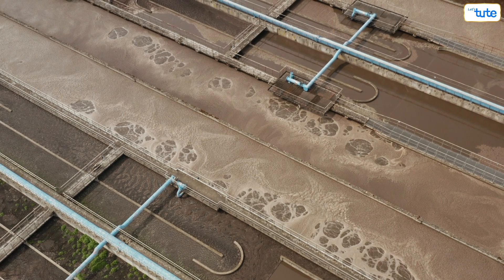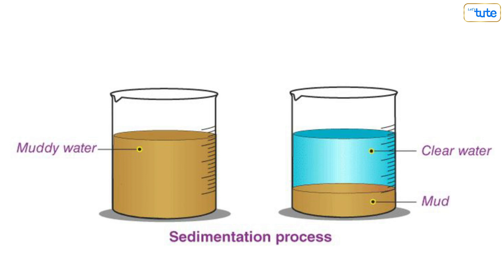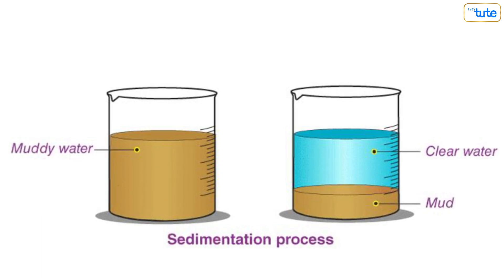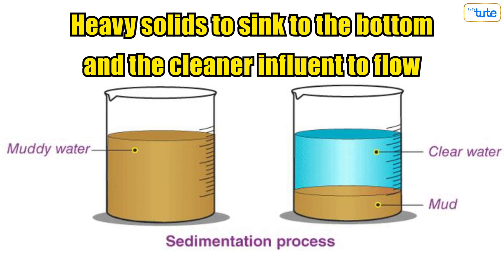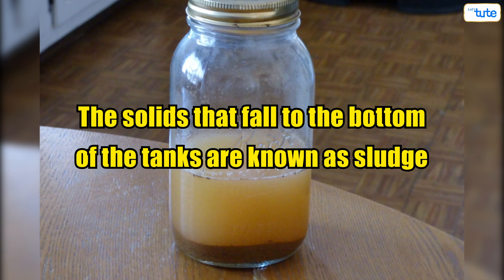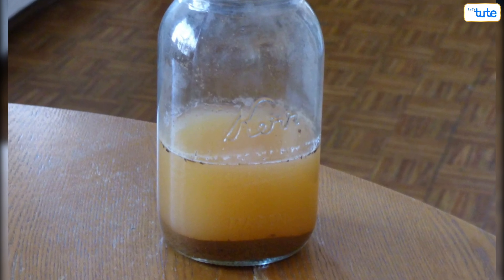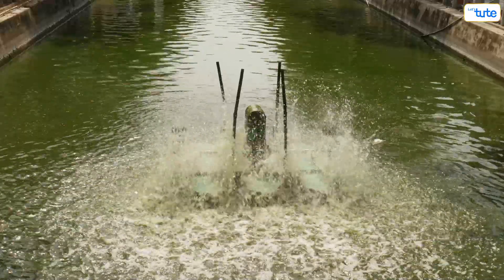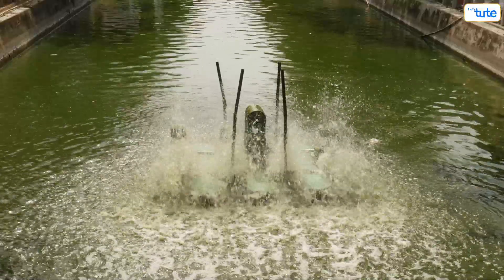The third step is called sedimentation. It is a process of settling after grit removal — the influent enters large tanks that allow the heavy solids to sink to the bottom and cleaner influent to flow. The solids that fall to the bottom are known as sludge and are pumped out regularly. The sludge is then discarded after all the water is removed and is commonly used as fertilizer.